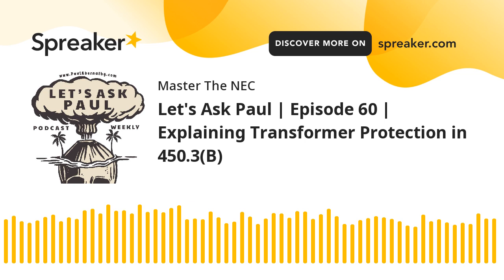Okay. Now, primary conductor sizing. Let's go on and do this. So we already know what's a given. We said it was a 45 kVA transformer. I'm going to use my rule of thumb, which is I'm going to treat it as continuous loads only, and I'm going to take the full value as a continuous load. And it might be somewhat less than that, because you remember, we're sizing that transformer based on whatever we calculated the loads were for that panel anyway, and then we selected the transformer.